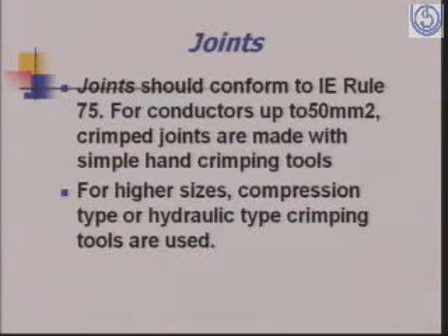Then the joints. Joint formation is very important because the losses in joints are very high, and if the joint is not properly made, it has been observed that the losses in the joints could be as high as 2 to 3% of the total losses. Therefore, the joint should conform to IE Rule 75.